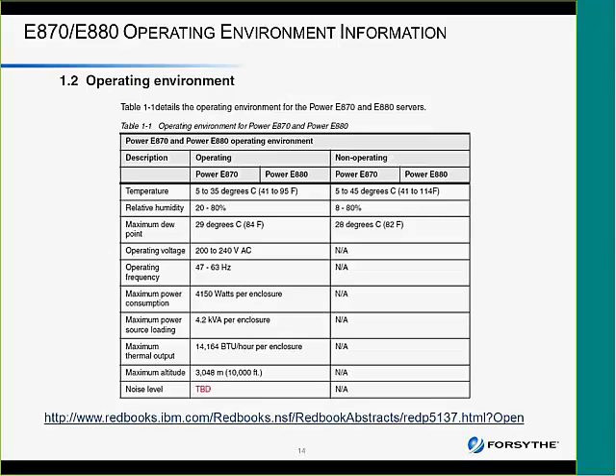So if you go with an E880 and later this year you go to 4 nodes on it, you're going to need a lot of PDUs. And this is one of the reasons why we're recommending that people start to seriously think about moving to the 60 amp PDUs, which at least can handle 9.6 kVA. And again, basically what I do is I go to the Red Book and then I just do a search on watts or kVA, and it brings me down to this section, which is always under operating environment.